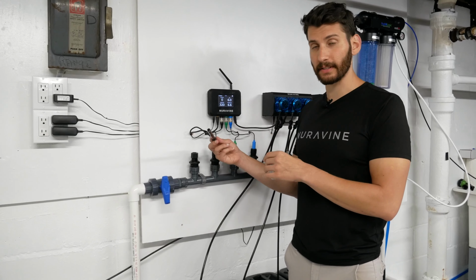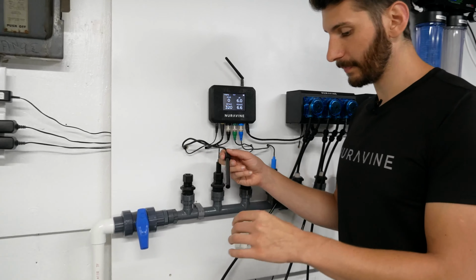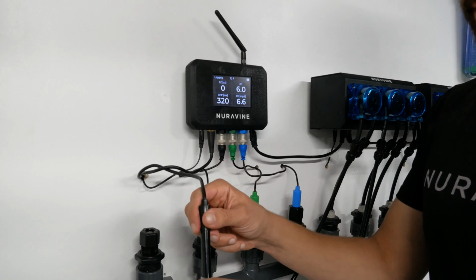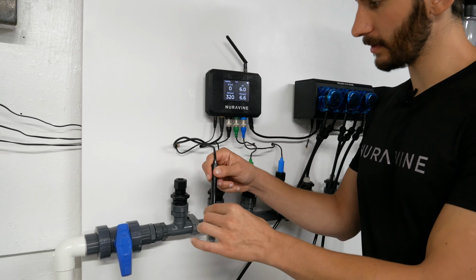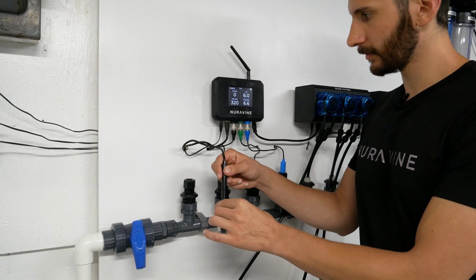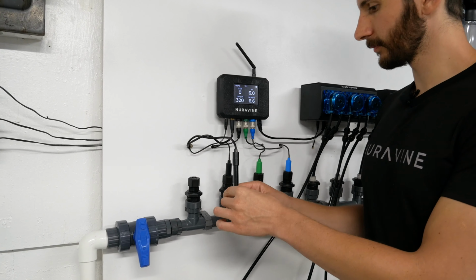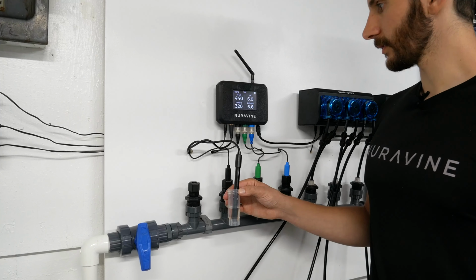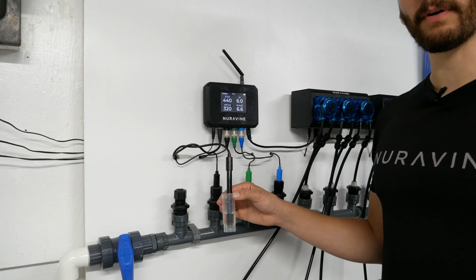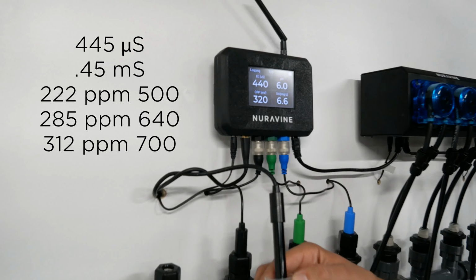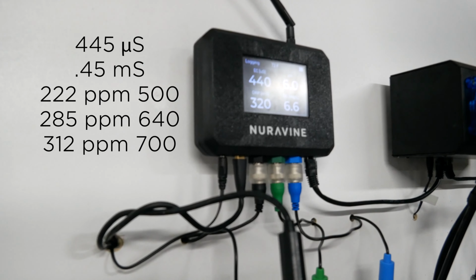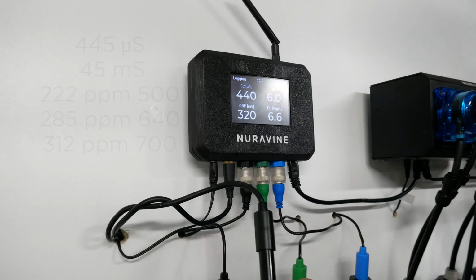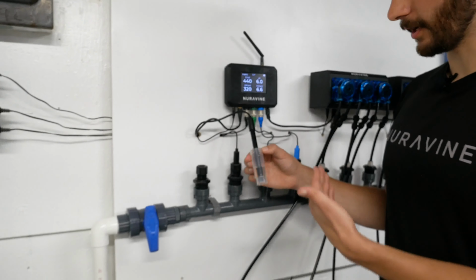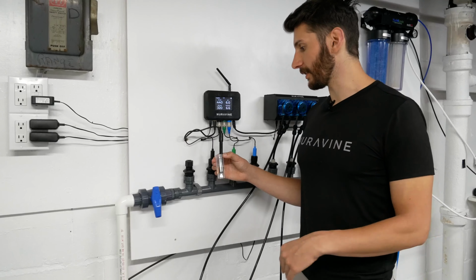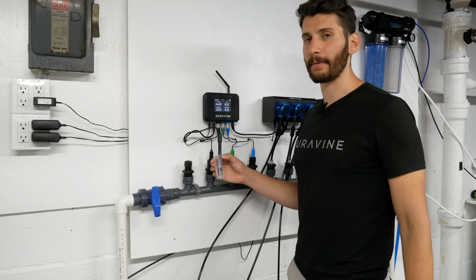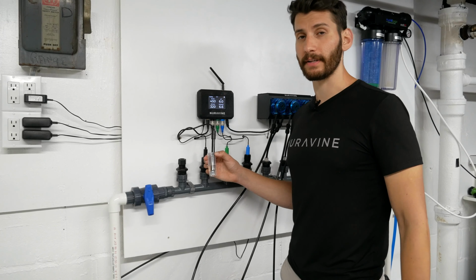So actually this is also a good test. See that it's 0 when it's in the air. That's also a good thing to notice. And now I'm going to put it into here, shake it around. Okay, cool. So we're hitting 440. Now this is a 445, and so if you're seeing somewhere between 440 and 450, you're right on the money. So we've seen that it's good in all these different numbers, so we're very happy with our EC calibration, and we can move on to the next step.